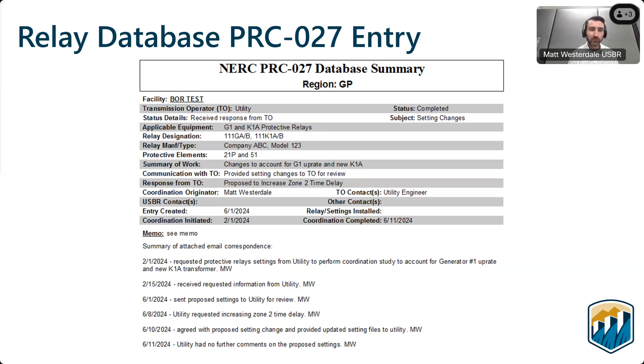Continuing with our relay database, by entering all this information we have four relays where we have proposed setting changes for this example: primary and backup relays on our generator, and primary and backup relays on our transformer. These setting updates resulted in additional PRC updates as well.